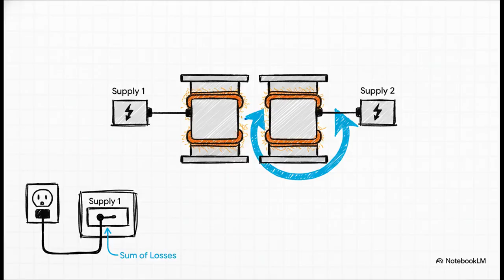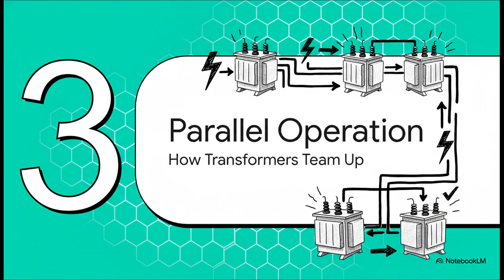It's brilliant! So our transformer has passed its physical. We know its characteristics, we know it can handle the heat, but out in the real world, on the grid, transformers rarely work alone. They're team players, so the final step is to make sure it can actually play well with others. The best way to think about operating transformers in parallel is to picture two people carrying a heavy couch. For it to work, they have to be matched up, right? If one person is way taller than the other, they're not going to share the load properly. And most importantly, they absolutely must lift in the same direction. Because if one lifts up while the other pushes down, well, that's going to be a disaster.